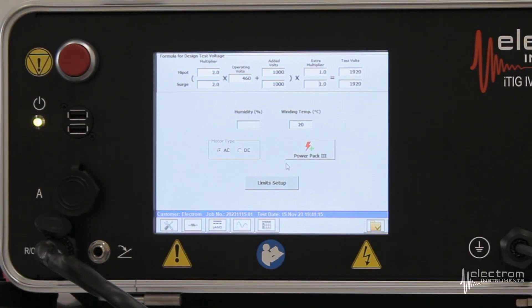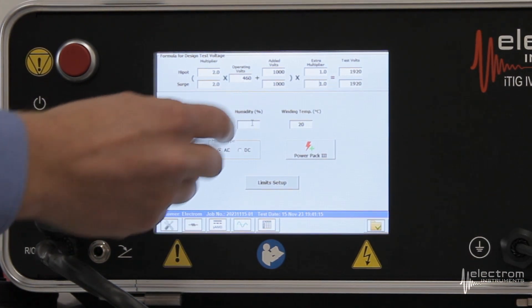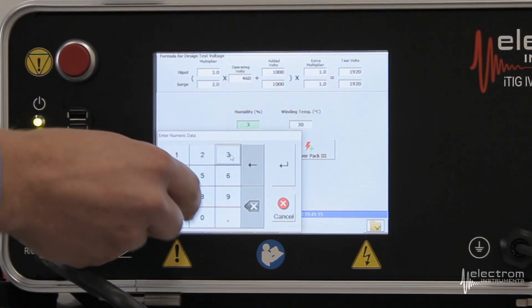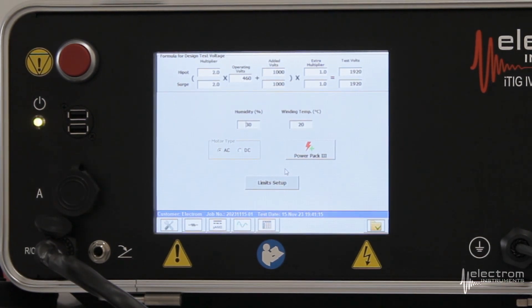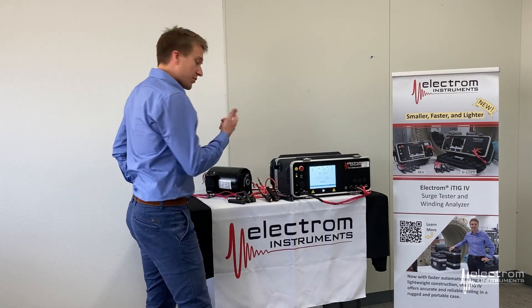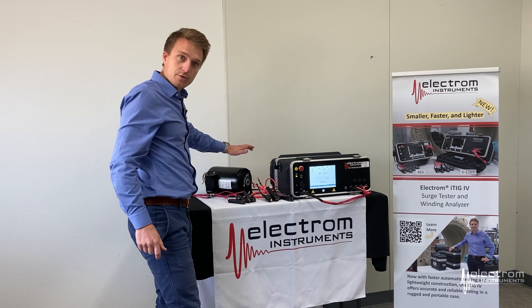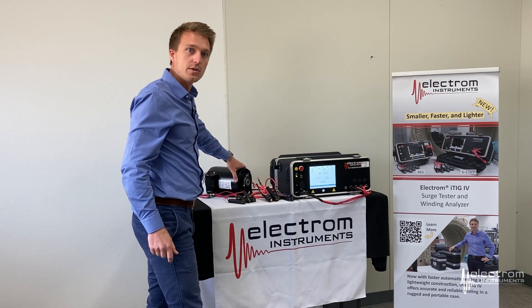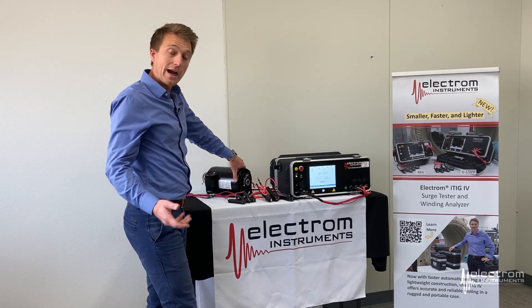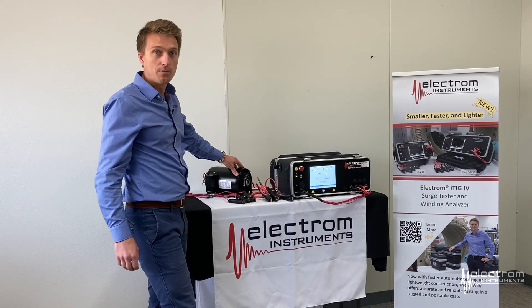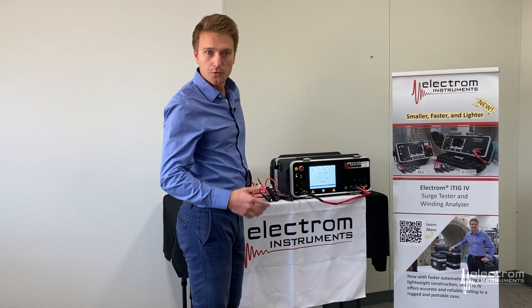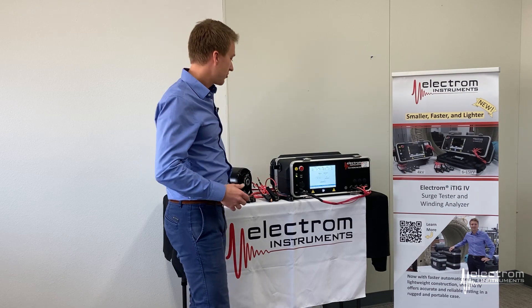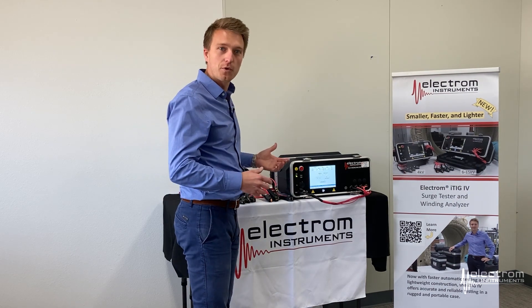Next, enter the humidity — that's the air humidity. We're in Colorado on a nice dry day, so about 30%. Next is the winding temperature. Note this is the winding temperature, not necessarily the ambient temperature, so using an IR gun to determine the temperature of the winding is very important here. We use that to correct the winding resistance measurement as well as the megaohm measurement. If the motor has been sitting in your workshop or storage, you can assume ambient temperature, but in many cases it will be warmer or colder.